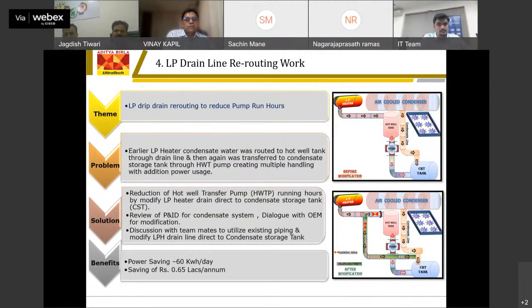This is one of the innovative projects which we have done, a rerouting of the line of LP heater drains. Earlier, the LP heater drain was connected to our hot well, and through the hot well pump it was transferred to our CRT tank. Now we have directly installed a line from the LP heater to CRT, through which we save the running of our hot well pump, which gives an energy saving of 60 kilowatt per day, and resulted in 0.65 lakh per annum saving.